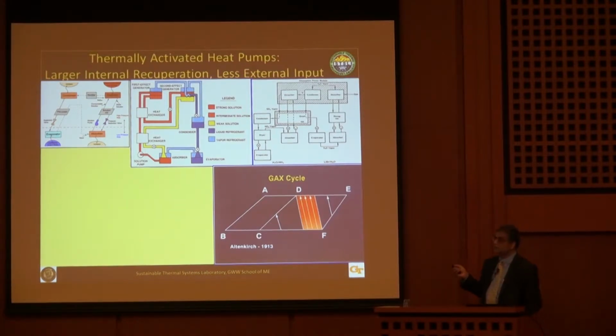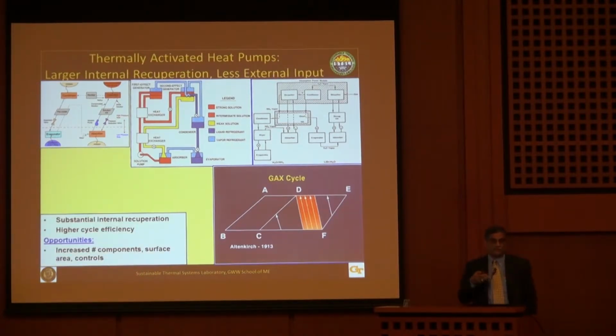Here's a dual cycle which does something similar: you run a lithium bromide cycle, use the waste heat from there to run an ammonia water cycle. Then there are generator absorber heat exchange cycles and so on, with substantial internal heat recuperation to provide higher cycle efficiencies. But this also means an increased number of components, more surface area, more cost, and more complexity and controls.